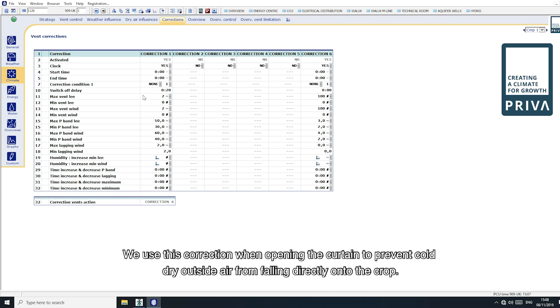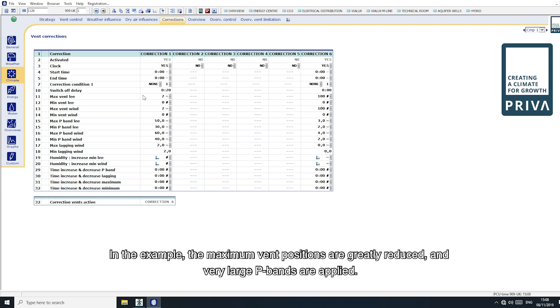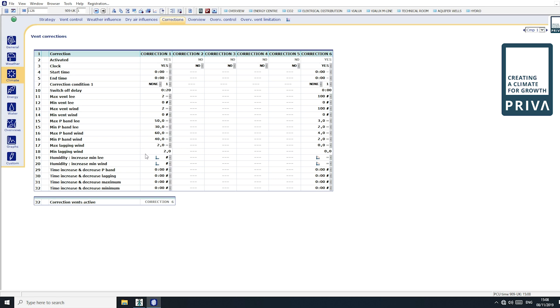We use this correction when opening the curtain to prevent cold dry outside air from falling directly onto the crop. In the example, the maximum vent positions are greatly reduced and very large p-bands are applied. A big lagging for the wind side is also set.